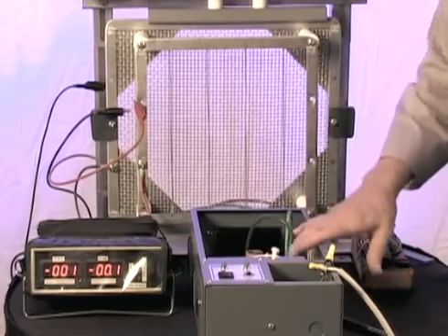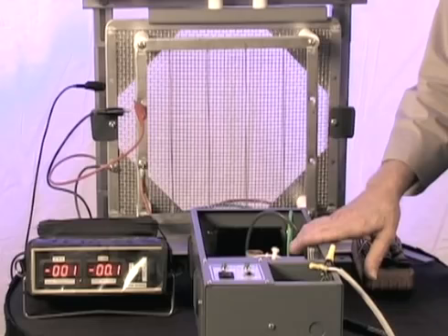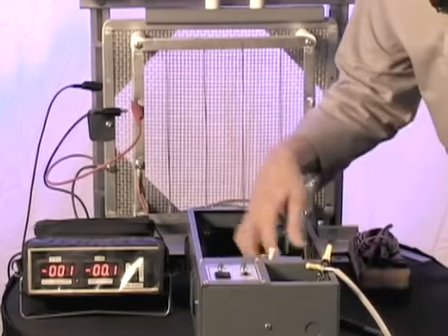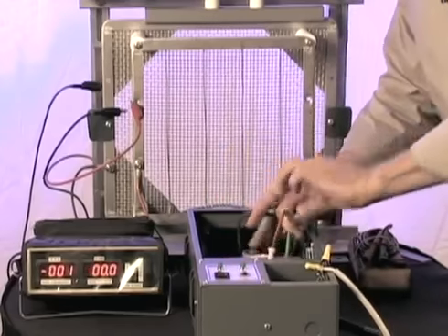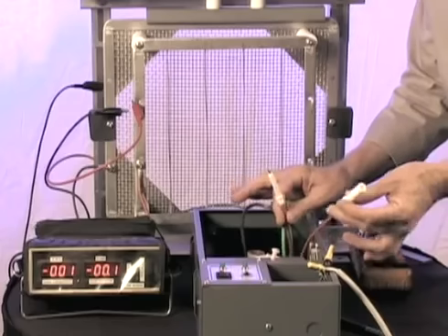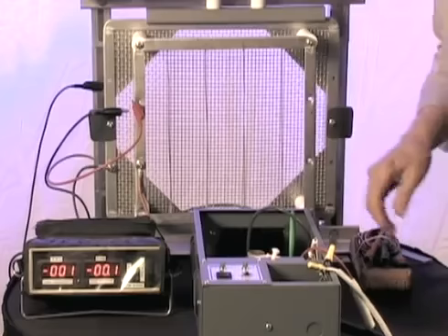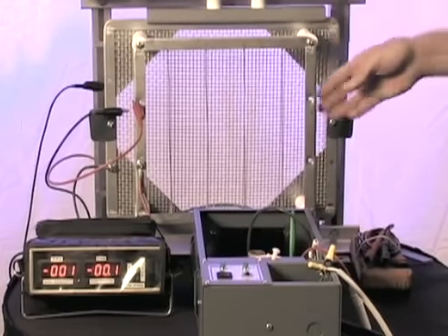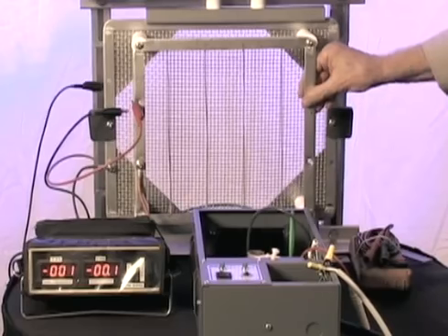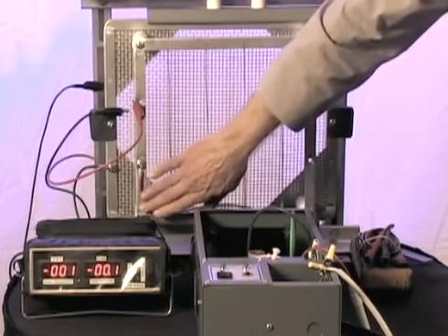If at the screens you measured no high voltage, the next thing you want to do is to go internal into the unit and pull apart this connector. If pulling apart this connector brings this high voltage light on, then you have a problem at the screen set with the high voltage screen somehow being shorted to ground. It's a very simple arrangement with the high voltage wire coming in and with the electrode as it is.